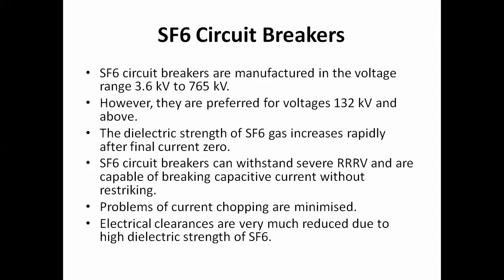So you can see that over a wide range of voltages, we can use this type of circuit breaker. However, they are specially designed for voltages of 132 kV or above. I can tell you that this type of circuit breaker can work over a very wide range of voltages, about 3.6 kV to 765 kV, but it works effectively and efficiently when the voltage is about 132 kV. As I have already written down, the dielectric strength increases rapidly after the current becomes zero. So these are certain advantages or properties of the SF6 circuit breaker. On the basis of this, we can use the SF6 circuit breaker in the generation part, in the transmission part, as well as in our distribution part. Okay.